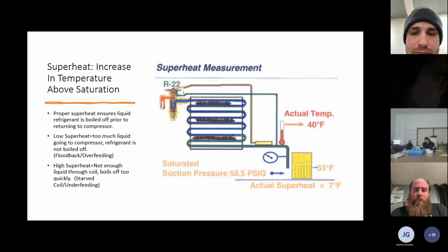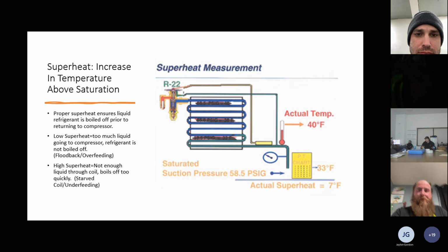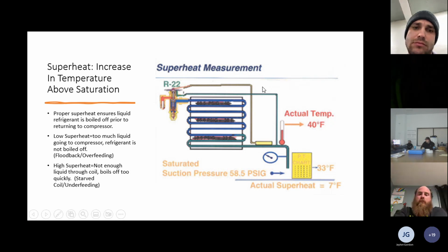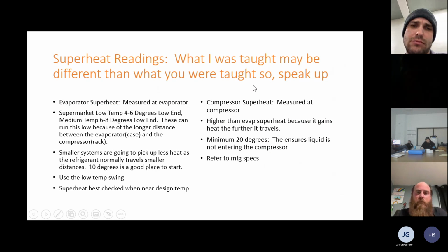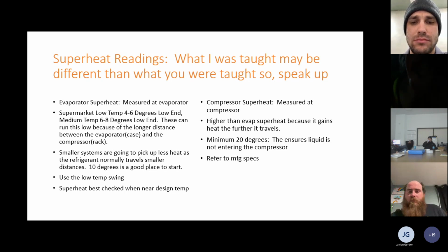But depending on the gas, 448 is a gas that's got a huge swing, with high drive, that valve. You also gotta remember, you want to set your superheat when it's as close to set point as possible, because when it's just cycled on, it's absorbing more heat. So that valve is going to be wider open because it's getting a hotter reading on that bulb. That's why you always set it when it's closest to your set point.